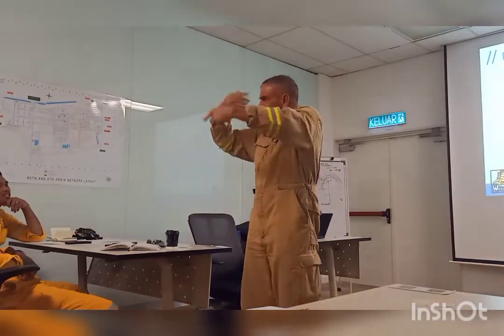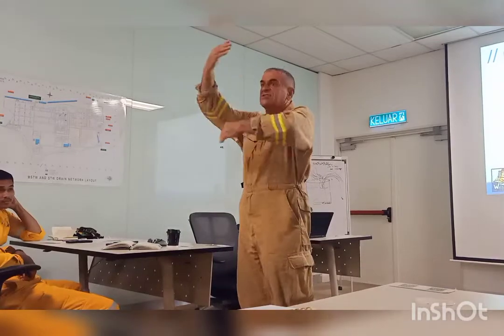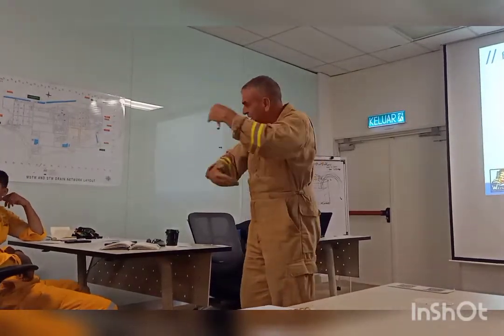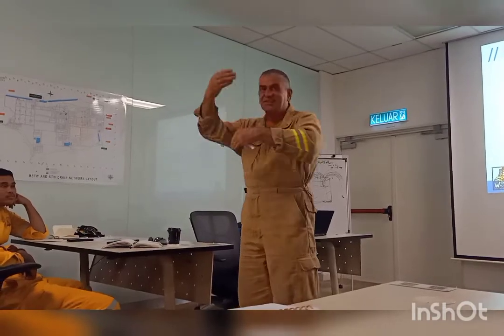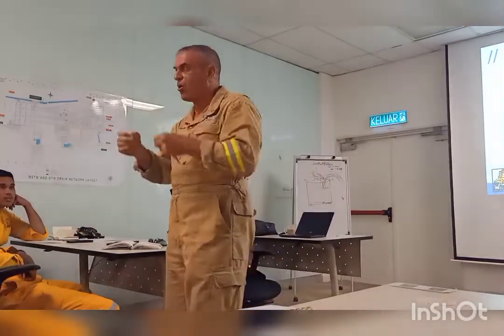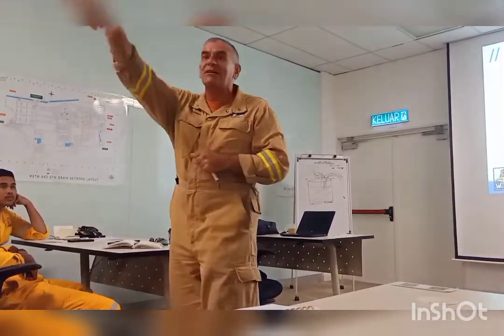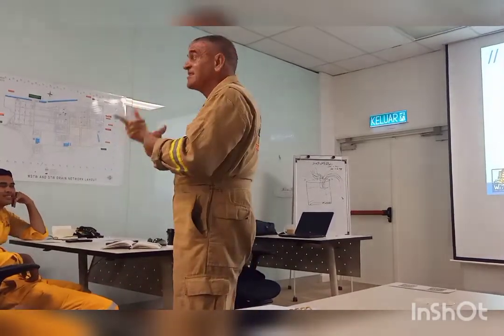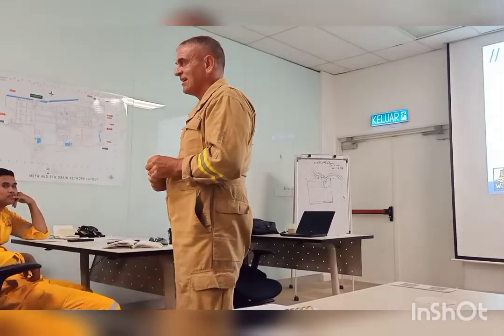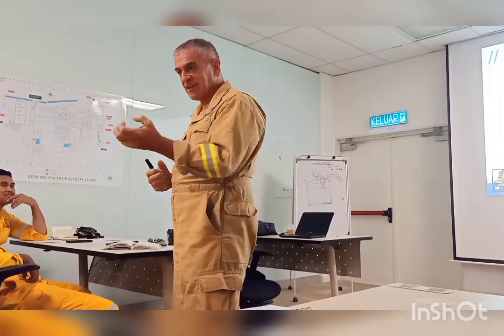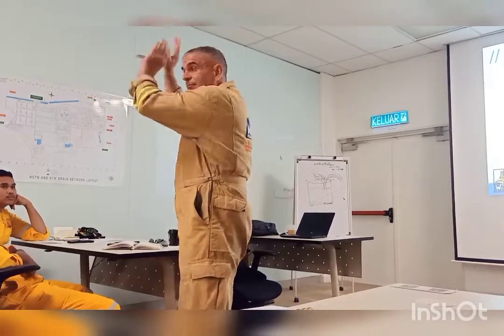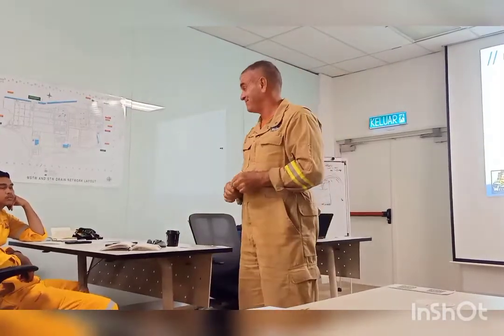You'll see the smoke starts to change, and the smoke will start to roll a bit more. You call it guling? Yeah. So it gets grey, it starts to roll, and you'll hear crack, crack, crack. These are signs that the water is starting to get hot. And that's normally the time when we see that start to increase, that's time for us to leave. Keep the monitors, leave them there, keep them running, we move away.